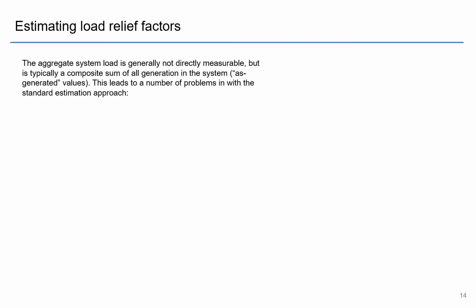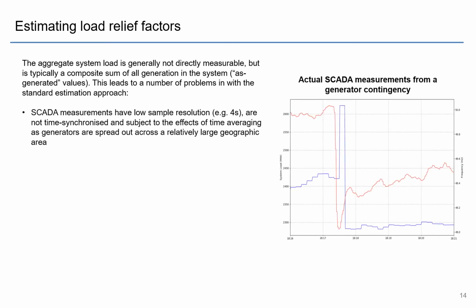The problem is that the aggregate system load is not directly measurable, but is normally a composite sum of all the generation in the system, the so-called as generated values. This leads to a number of problems with the standard estimation approach. The first is that SCADA measurements have pretty low sample resolution. It's 4 seconds in the Swiss system, they're generally not time synchronized, and they're subject to the effects of time averaging as generators are spread out across large geographic areas.